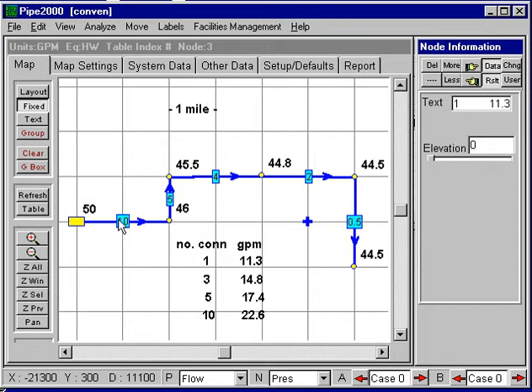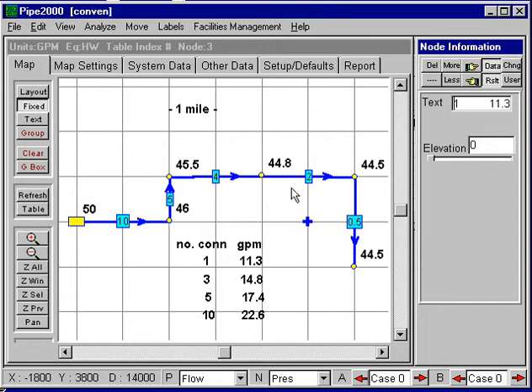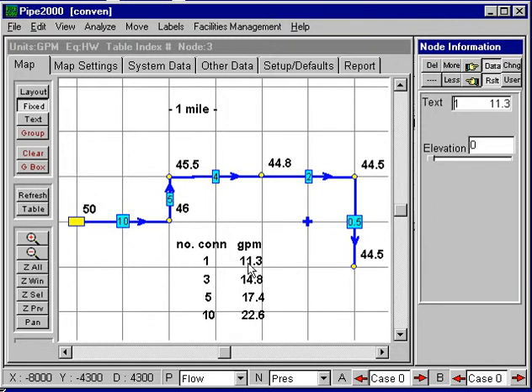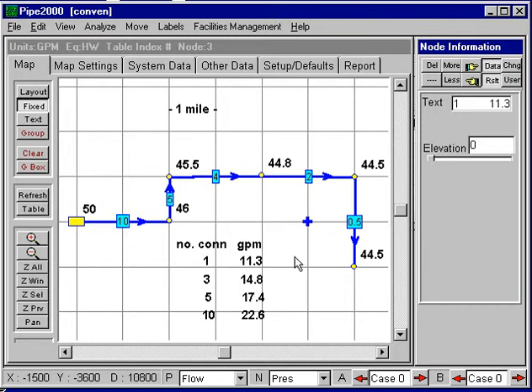But now, if we use the peak demand diversity concept, which states that we should have an amount of flow based on the number of users — this is the amount of flow recommended: if you have one user, you have 11.3 gallons per minute, and so on. So we're going to use this curve to allocate the flows.